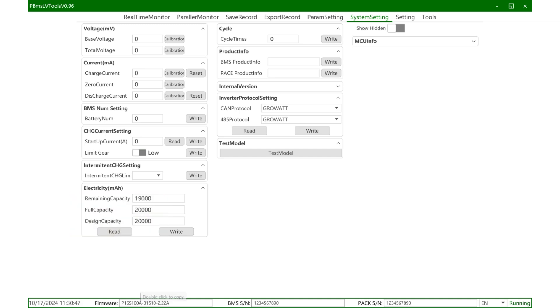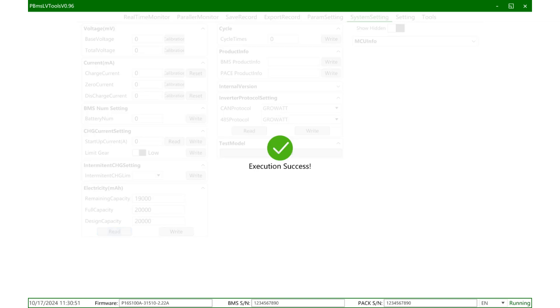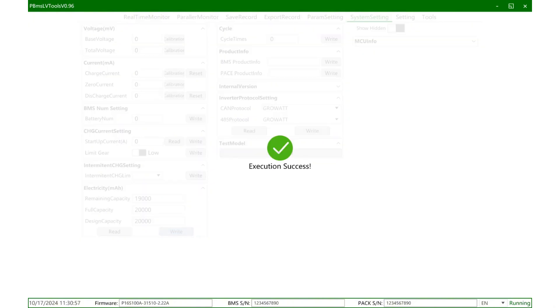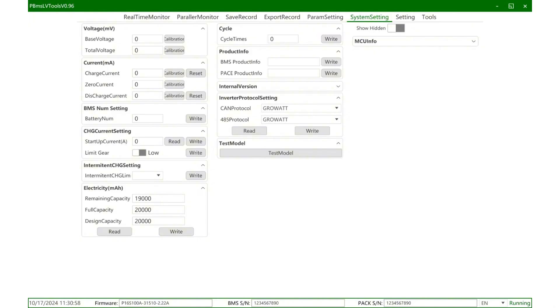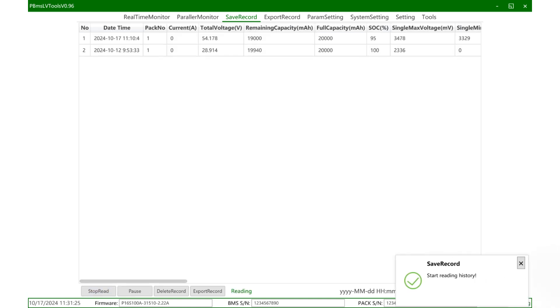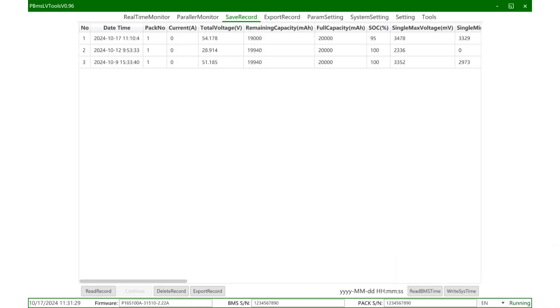There is also a language switching function here. There is the remaining capacity. Generally, you only need to modify this design capacity because the remaining capacity and full charge capacity are learned through charge and discharge cycles. Be set only when the battery cell capacity changes. For example, if a 200Ah battery cell is used but the written design capacity is 100Ah, in this case it cannot be learned. It is necessary to ensure that the design capacity and the actual capacity of the battery are within 10% difference before learning can be successful. Generally speaking, it is not recommended for customers to set it by themselves. You can communicate with our engineers in advance about the actual capacity of the battery cell.